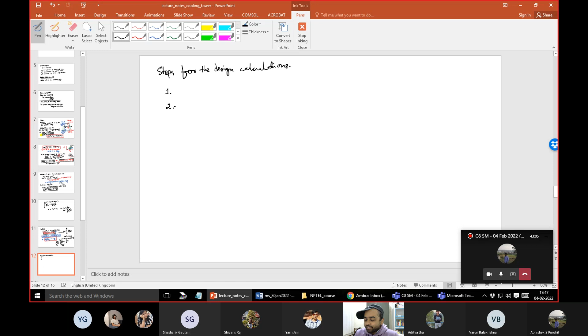So this is one big advantage here, that you do not need to draw the equilibrium curve separately. If you just take your psychrometric chart, the 100% saturated line will give you the equilibrium line, and you can start working on the operating lines from there on. Now the fourth step, after you draw or identify the equilibrium line, is to identify the lowermost point, which is the inlet of the air and the outlet of the water. Most likely this information will be known to you, because the outlet of the water is the desired temperature that you want from your cooling tower design. Right, so that information will be known to you, and also the inlet of the air, which is the surrounding air that will be coming, will also be known to you.